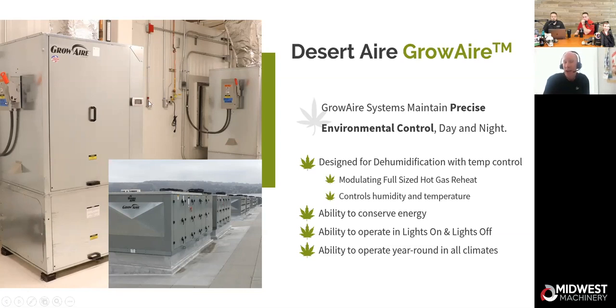So now they're not air-cooled units, but they're water-cooled. He's got a water line running around to it, and we're just rejecting our heat. Whatever waste heat we have from the equipment is being dumped into that water loop that goes out and then is being cooled by a cooling tower. But you know, we can do these as air-cooled, water-cooled, but these two units work together to maintain that environment on the other side of the wall.